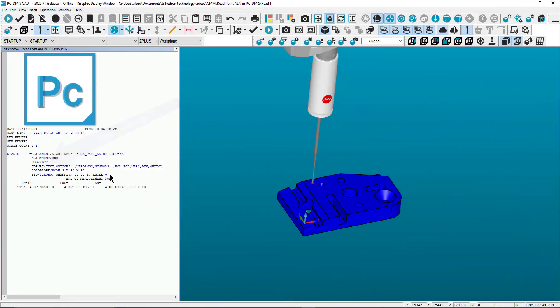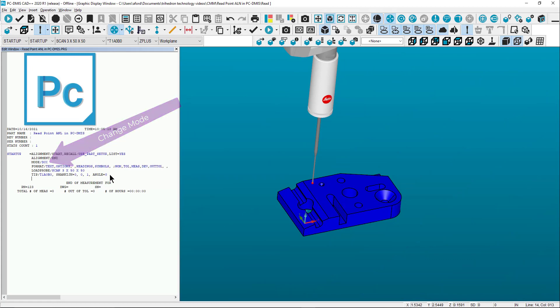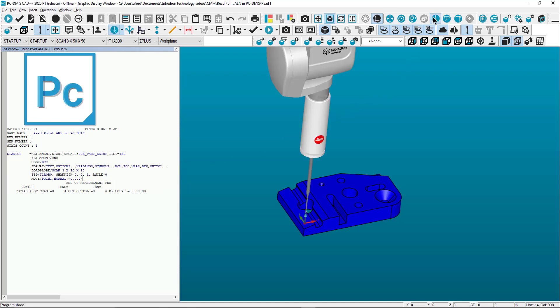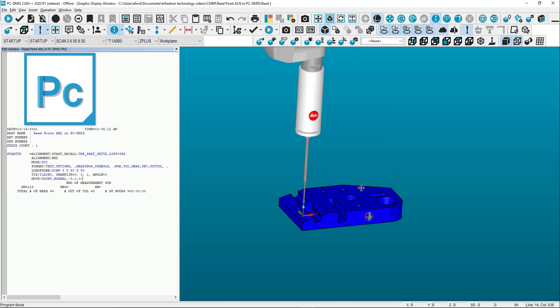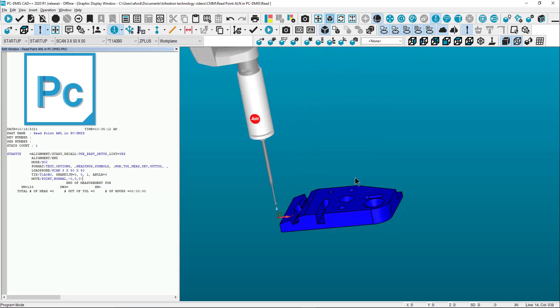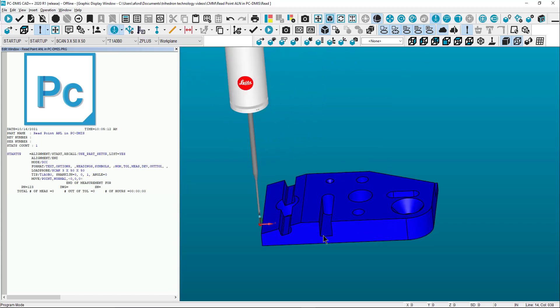First, start by changing the mode to DCC, then create a move point X0Y0Z0 and press CTRL E. This will move the theoretical CMM location to the CAD origin. Now that the probe is positioned, select the program mode icon or CTRL F4. This will display the probe CAD.